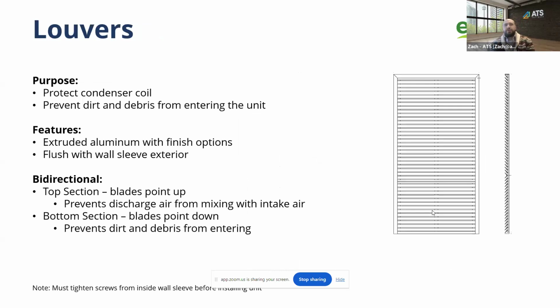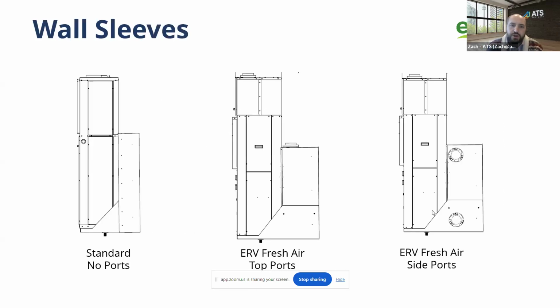And a question coming in there actually on the wall sleeves, a couple of questions. Yep. So first on the ERV intake and exhaust, are those ERV intake and exhaust into the wall sleeve and not the standard wall box or the louvers? Yeah, so we don't need a wall box or a separate consideration for that. So I think there's another picture coming up, but basically the 2 connections on the top of the unit in this one, or one in each side. So in very good representation here, the condenser fan motor sits right here. So it's pulling air in through the condenser coil and then pushing it back out this way. So this separator right here, this is fresh air and this would be exhaust air. The condenser fan motor is actually doing the work for us. So no, we don't need an additional wall box or any type of louver on the exterior of the building. The sleeve is doing everything for us.